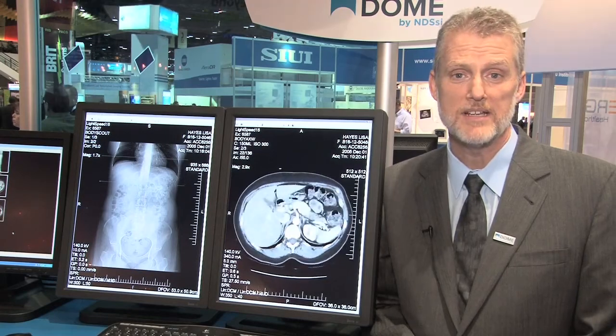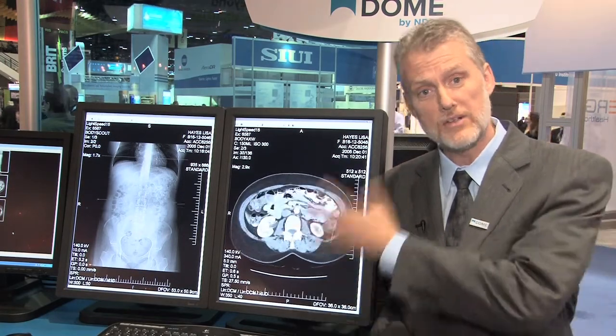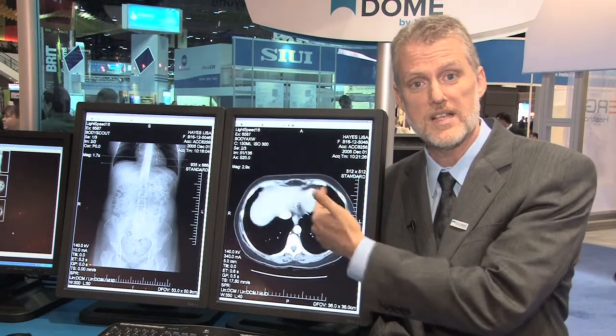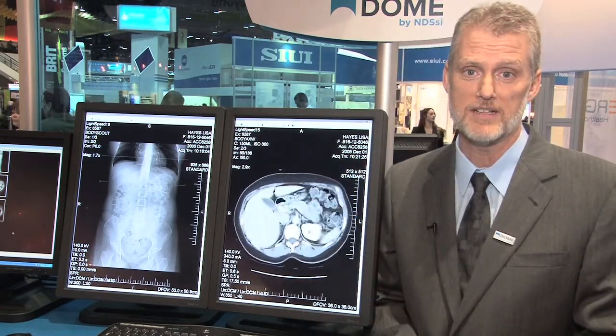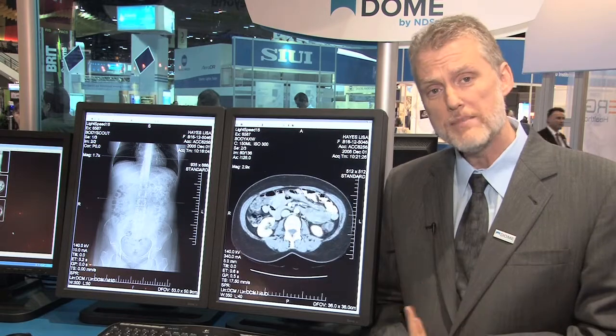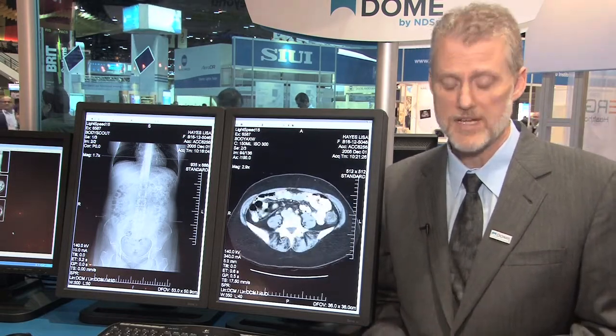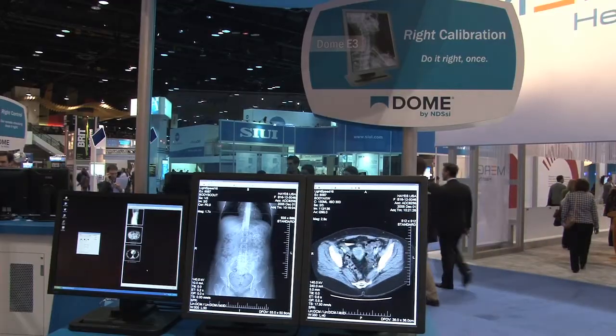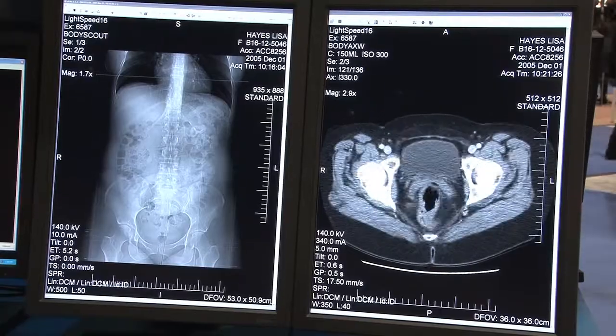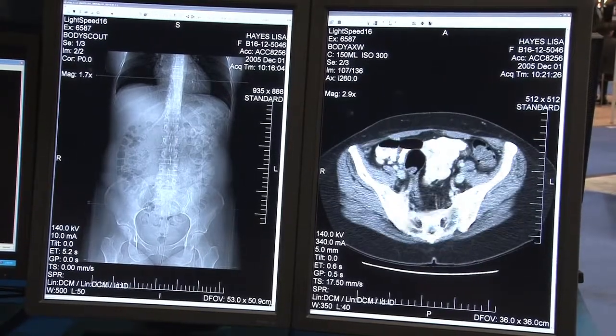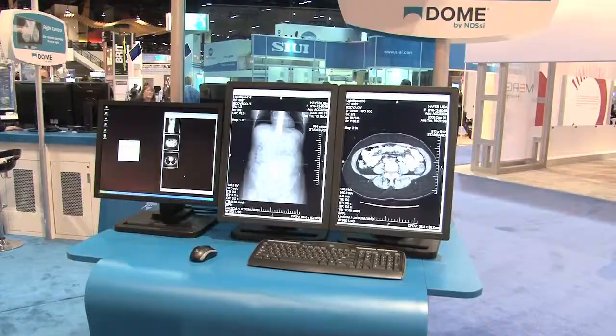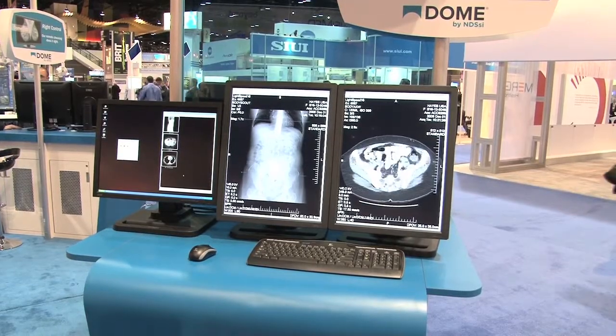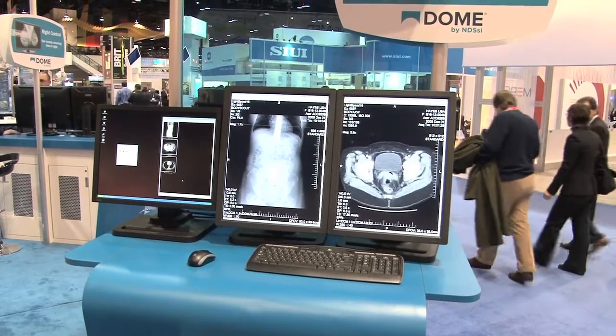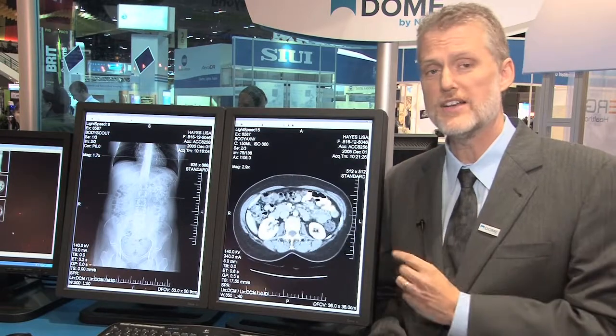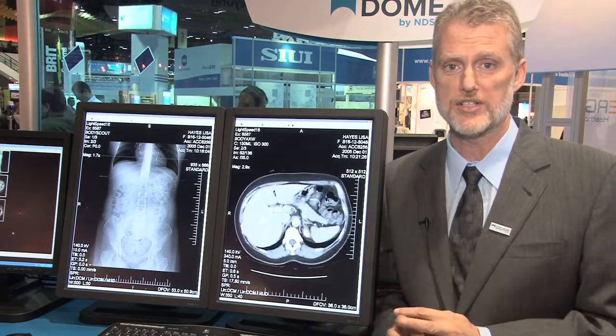To calibrate a display, DICOM recommends that you put up a gray screen with DICOM test targets and measure with a photometer from the center of the display. To do it automatically, you need to make a compromise. You either need to compromise where, when, or how you're going to do that calibration. We felt that compromising the where and how was wrong, so instead, we compromised the when and decided to do this in the factory where we could carefully control the calibration.